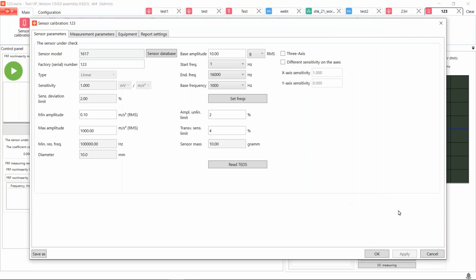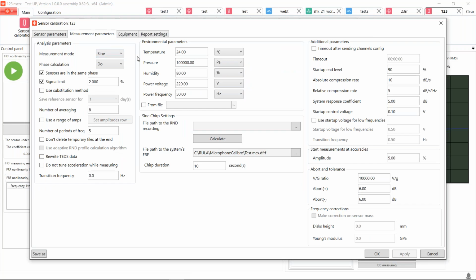In the Measurement Parameters tab, you can enter calibration parameters and select the measurement modes. The following methods of calibration are available in TestUp: sine, random, manual, and substitution. If the sensor under calibration is mounted directly on the reference sensor, such a procedure is called back-to-back calibration. Just a few words to highlight the difference between these methods. Usually in a back-to-back calibration, a sine wave is used to excite both sensors. When the sine wave is being generated on the shaker, the output signals of the reference sensor and the sensor under calibration are measured. The procedure takes about 10 minutes.